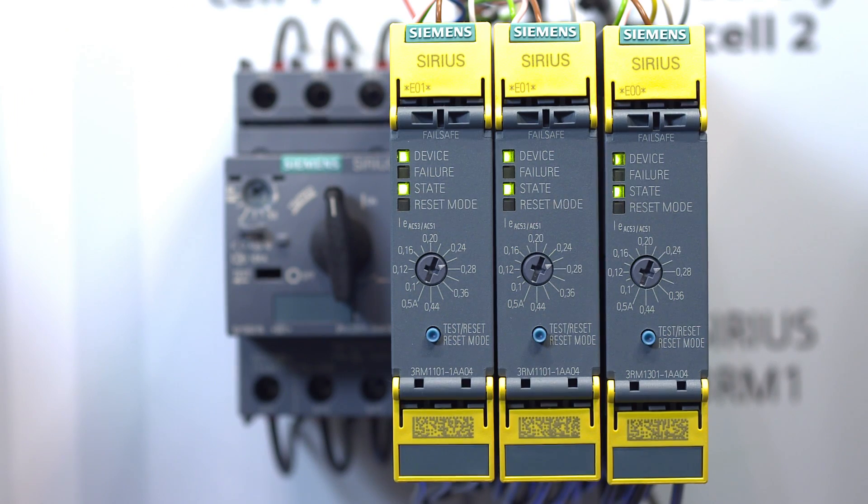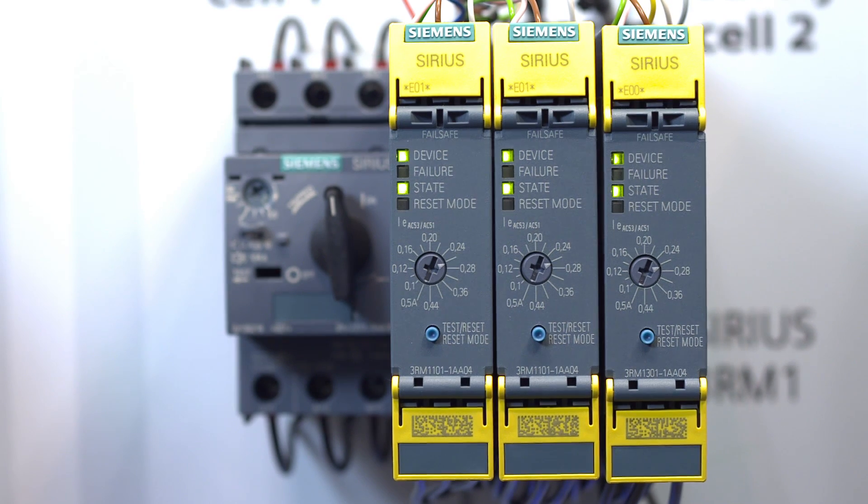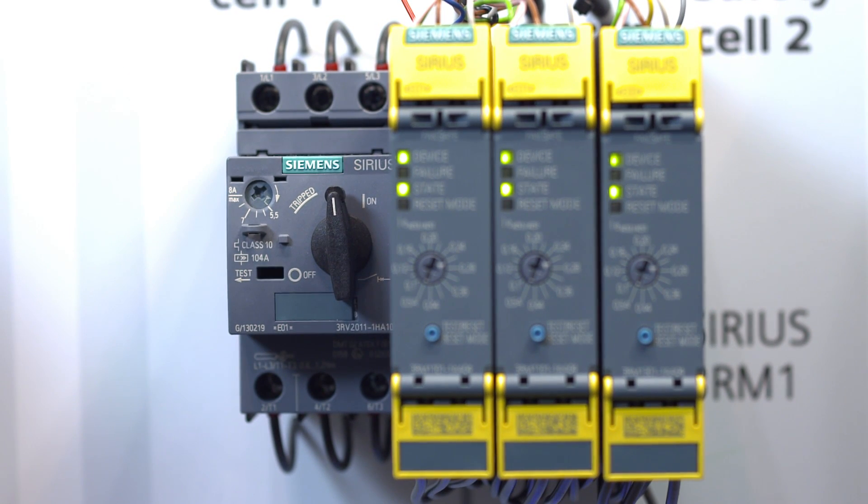Now we offer you a further highlight. The Sirius 3RM1 motor starter is also available with safety functionality and ATEX certification of the overload protection. As well as these functionalities, the new fail-safe motor starter also continues to offer the functions direct online start or reversing start with integral solid-state overload protection depending on requirements. This saves time and wiring costs and it reduces the potential for errors during configuring, assembly and commissioning.